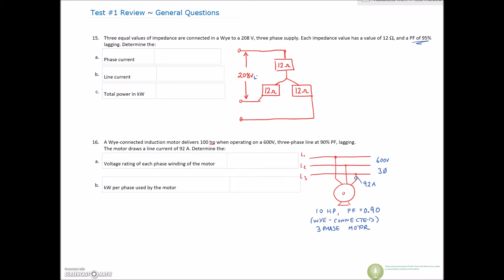This is a Y, so we know that for the Y we have two rules: I-line is equal to I-phase, and V-line is equal to V-phase times root 3. So the phase voltage is less than the line voltage by a factor of root 3. We've already memorized that when we have 208 volts on the line voltage, the voltage on the phase is 120 volts.